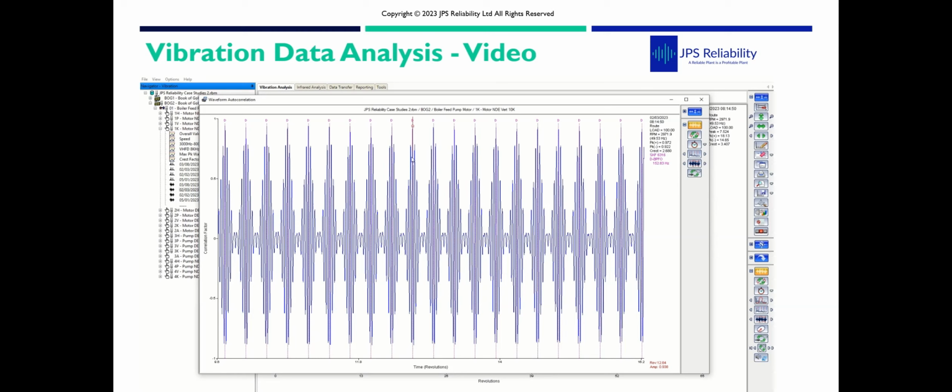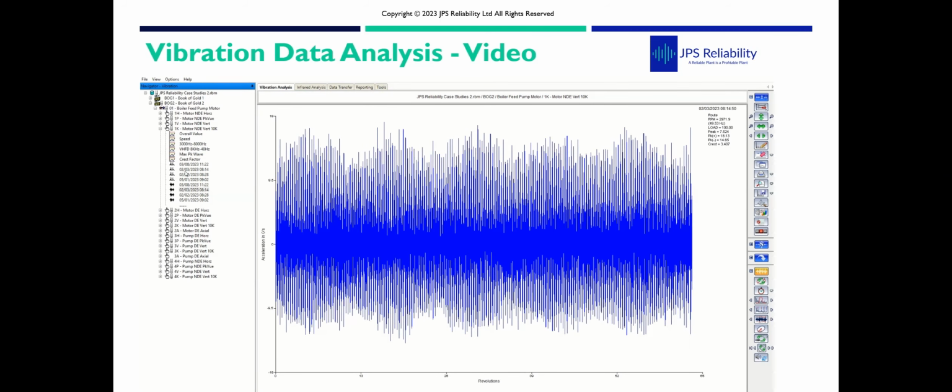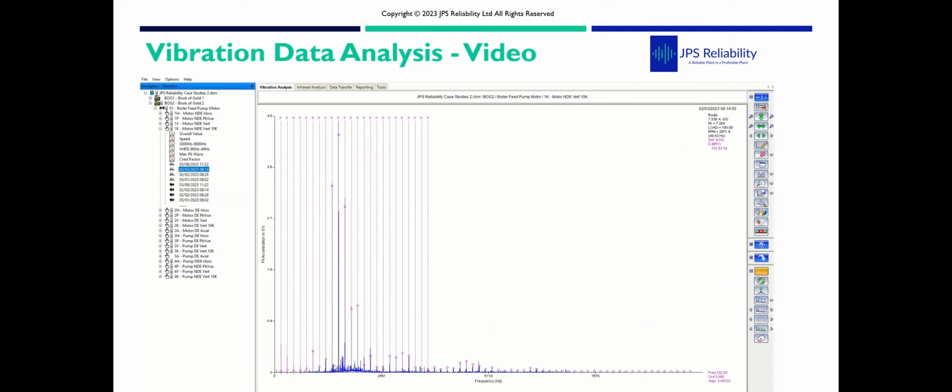Now, what is that frequency? Well, if we set our cursor to a reference cursor, toggle to sidebands, then we can actually bring out some sidebands to have a look. So if we zoom in to one of the pulses, bring our sidebands out to the top, there we have it perfectly. So this outer race defect frequency, which is not a normal outer race defect frequency, is occurring on the frequency of 1599 hertz. Now, when we go back to the spectrum derived from the waveform, look at this mound, it is around 1500 hertz. So that's our electrical drive noise, which is killing our bearing, giving us EDM, and hence why you get the hump sidebanded by outer race.